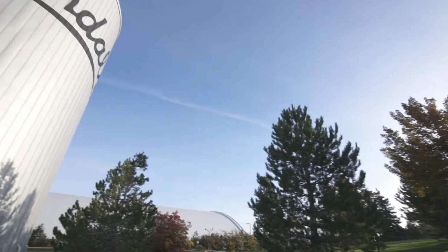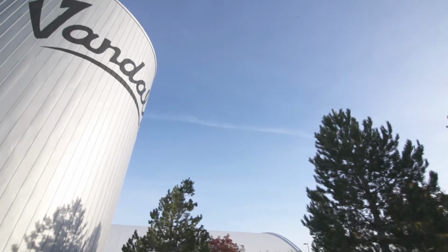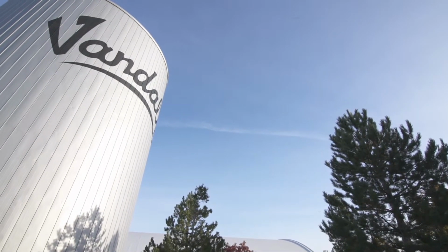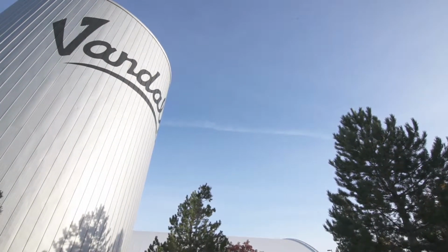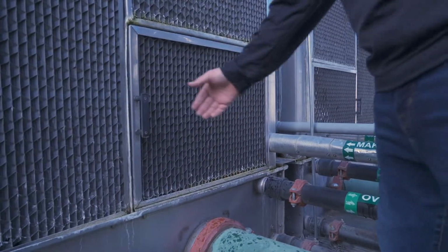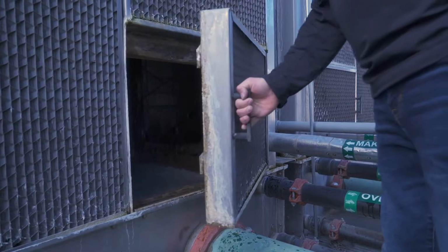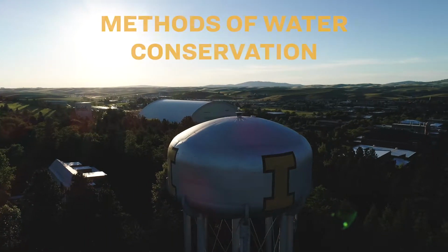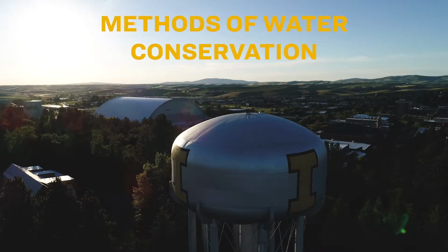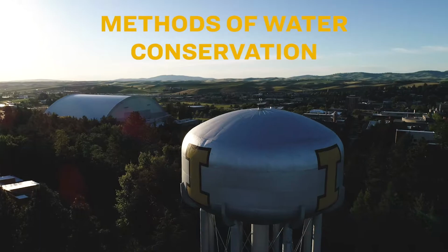The chilled water system is treated with a combination of biocides and corrosion inhibitors to increase the number of passes it can make through a cooling tower. This means we can run the same water through the cooling tower more times with treatment. This reduces the need for makeup water and ultimately saves a significant amount of water each year. We are continuously trying to minimize losses to our industrial processed water system.